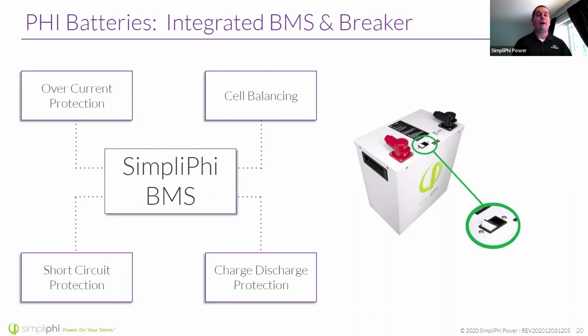In addition, all of our batteries have a BMS, which is a battery management system. So a BMS can serve many functions, but at a very high level, what a BMS is doing is providing some layer of overcurrent protection, meaning that you're not putting too many amps into the battery, too much power into the battery, or taking too much power or amperage out of the battery. Further, a BMS accomplishes cell balancing. So again, this battery is made up of a whole bunch of small battery cells that look like AA batteries or so. And in charging, they may not all charge exactly equally, but the BMS enables them to balance essentially during our absorb cycle to make sure that each of those cells is individually charged up all the way, resulting in a fuller charge for the battery as a whole.